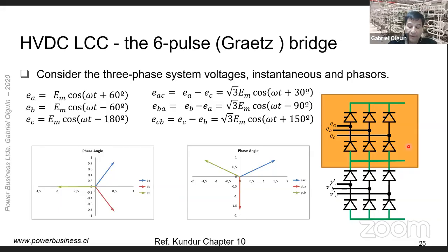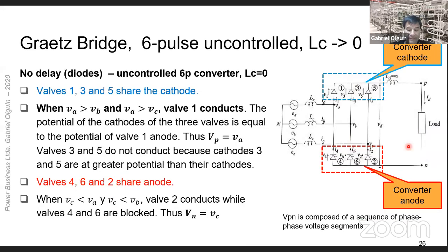Consider the ideal 3-phase voltages in this slide and the 6-pulse uncontrolled converter. To understand HVDC, it is necessary to understand the operation of the Graetz bridge, or uncontrolled 6-pulse 3-phase bridge based on diodes. This bridge is formed by 6 diode valves. Each AC phase is connected to the cathode of one valve and the anode of the other valve in the same bridge leg. The diode is a unidirectional current conduction device. It allows current to flow when the anode voltage is greater than the cathode voltage, and it blocks when the cathode voltage is greater than the anode voltage and current drops to 0.